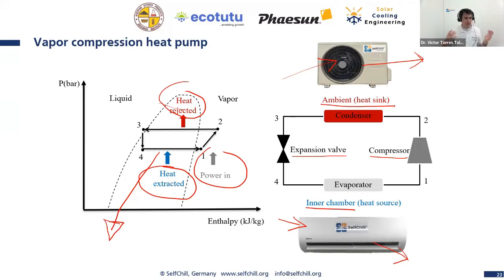So now, why do we need a refrigerant? Why do we need a condenser? What is this all about? Okay, you understood it with the air, and you saw that with the air we needed to go to 70 degrees, right? It's quite a high temperature. And what's the problem of the air? The heat capacity of the air is low. We need a lot of air to be able to transport the cooling energy inside. That's why we don't want to use air. We want to use a refrigerant. The refrigerant has a higher heat density, and it also has the ability to have a phase change.